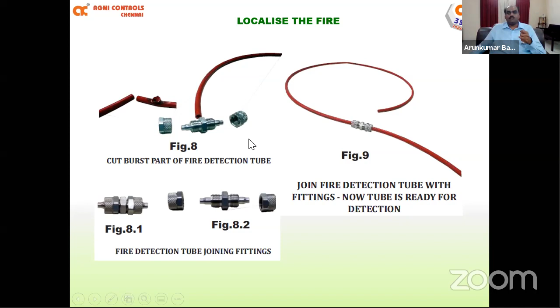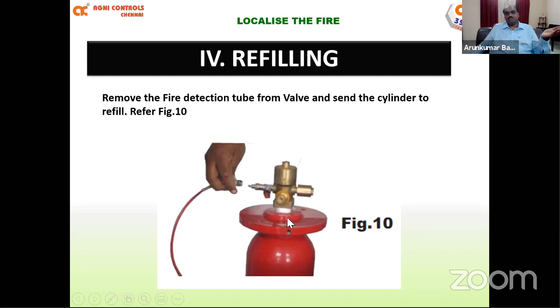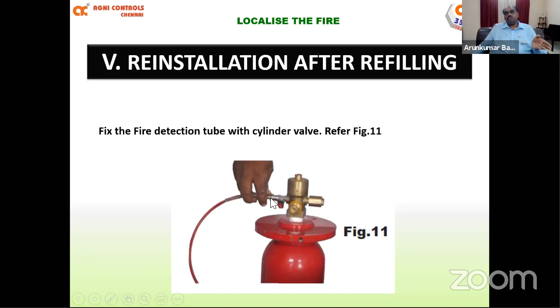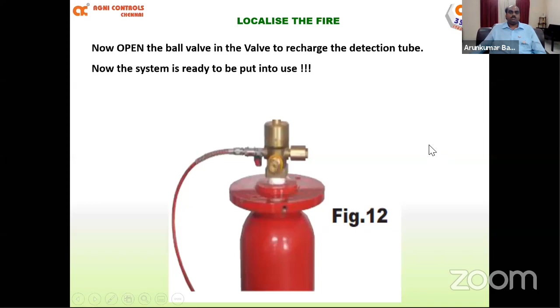Once you've done that, we also need to take the cylinder. Now the cylinder is empty. We need to take the cylinder for refilling. For that, close the valve, remove the detection tube from the valve, and then take the cylinder for refilling. If it is carbon dioxide, refill it with CO2. If it is nitrogen, refill it with nitrogen. Once it comes back, again the same procedure: fix back the detection tube and slowly open the ball valve, and the system will be ready for use again.